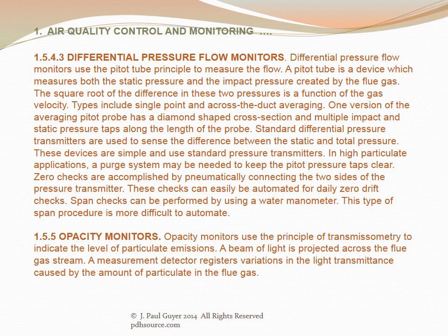Differential pressure flow monitors use the pitot tube principle to measure flow. A pitot tube measures both static pressure and impact pressure created by the flue gas; the square root of the difference in these two pressures is a function of gas velocity. Types include single point and across-the-duct averaging. One version of the averaging pitot probe has a diamond-shaped cross section with multiple impact and static pressure taps along the probe length. In high particulate applications, a purge system may be needed to keep the pitot pressure taps clear. Zero checks are accomplished by pneumatically connecting the two sides of the pressure transmitter and can easily be automated for daily zero drift checks. Span checks can be performed using a water manometer, though this is more difficult to automate.